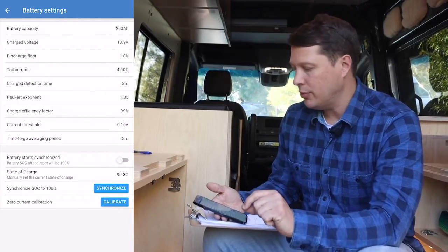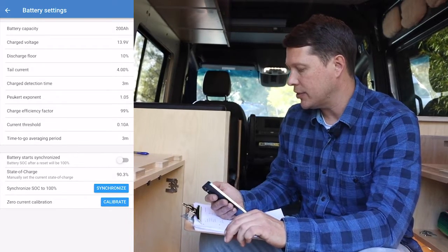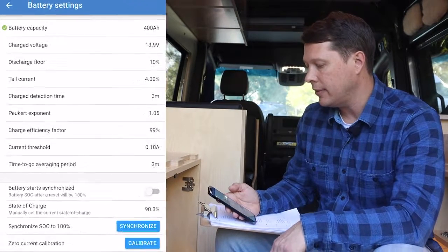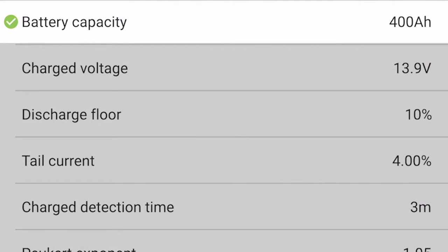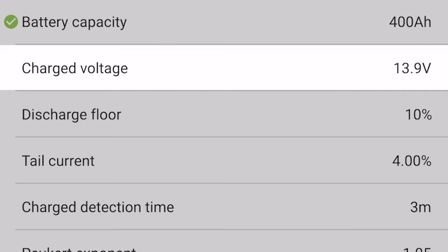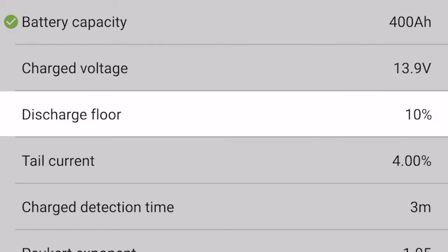So this is a really important one to set up properly. So you're going to need to go in and adjust how many amp hours of power storage you have. And so for this system, we're going to set that to 400. The next one, which is the charged voltage. The experts that I talked to at Victron say for these batteries, you'll want to put that at 13.9. So that's what it would consider to be the charged voltage for this battery before it goes into the next stage of charging. For the lithium batteries, the discharge floor, which is next, can be set to 10%.